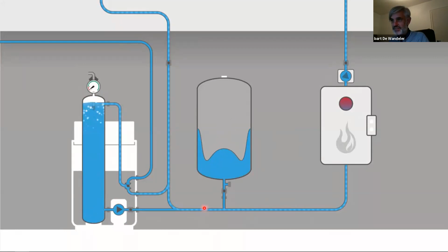You can see that the pump is constantly running in that mode. Here we have negative pressure, but the system pressure is controlled. Of course, if we degas, we make space — if we release air, we have more need of water, so the expansion tank can provide that water to the system. This is also controlled: if the pressure goes down and we have less water, we are able to start the degassing system.